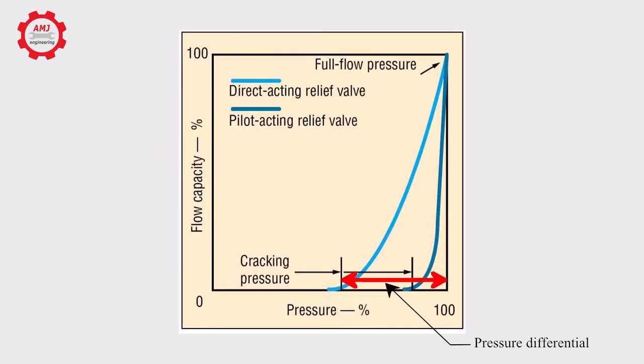The differential between cracking and full open pressure on direct acting relief valves is high. For this reason, they are not recommended for precise pressure control.